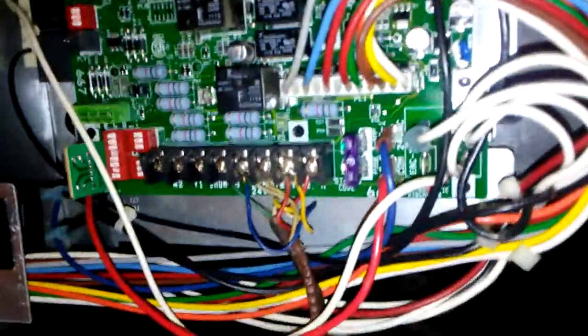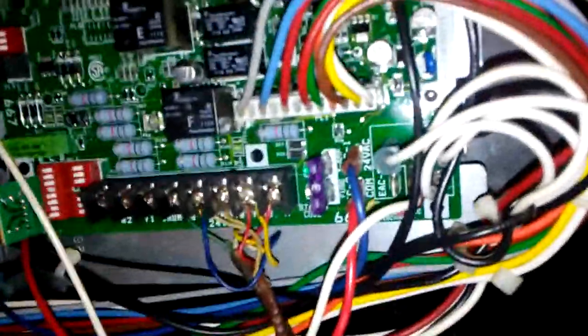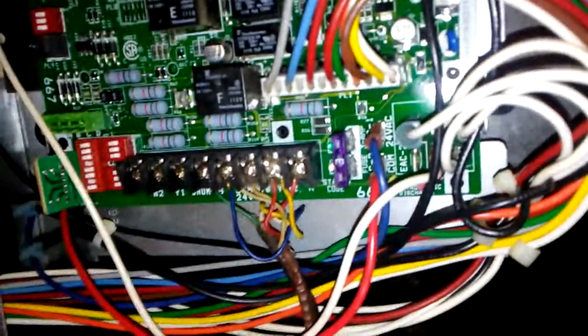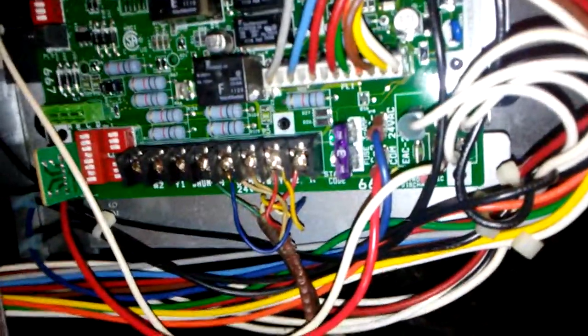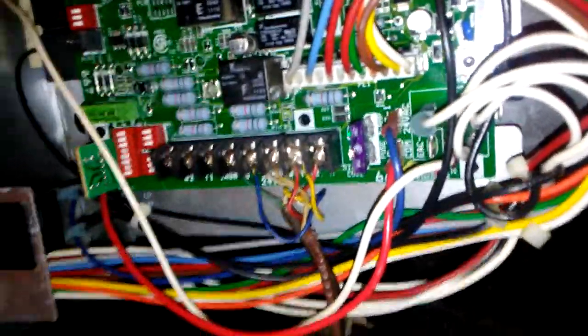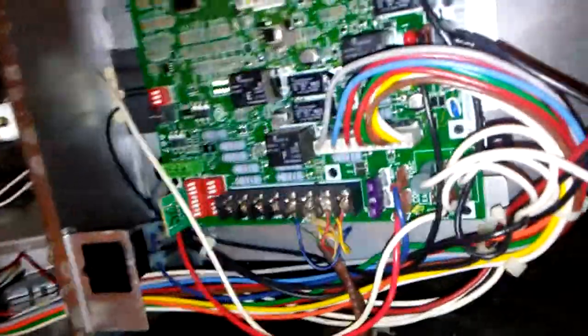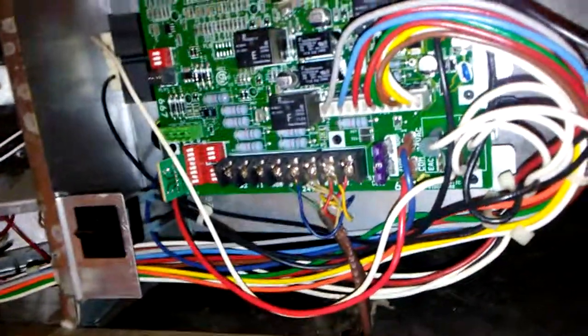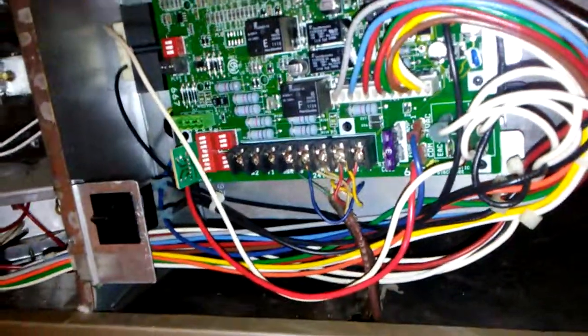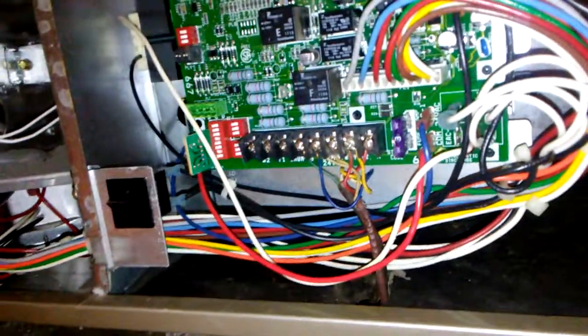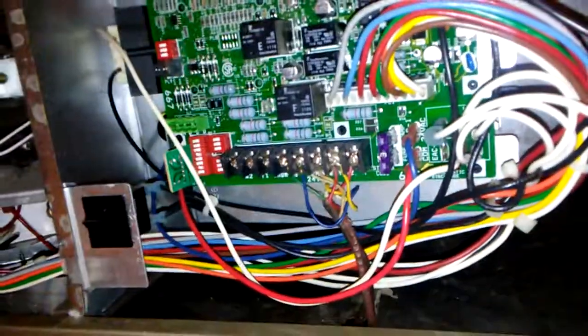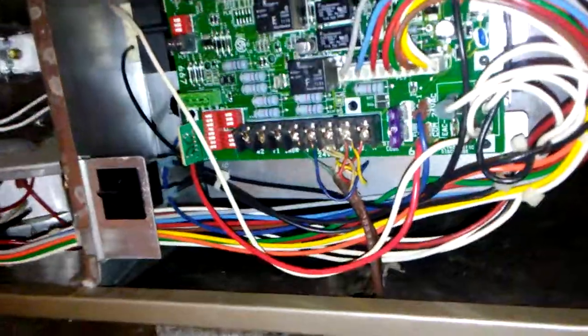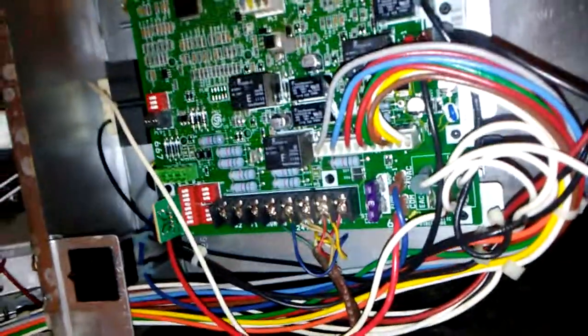I've been here rewiring this air handler to go on stage 2, or high speed, because being an old school house, the old system was to have one AC unit for both floors, and this house is one of those. I feel like it's not energy efficient to have this thing start off on low speed and then switch to high speed after 20 minutes of staying on. This is one of those adaptive mode type AC units.